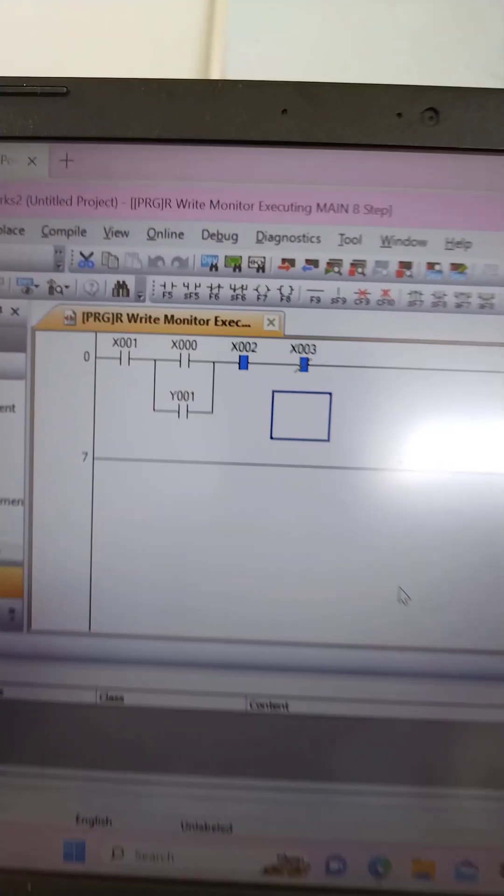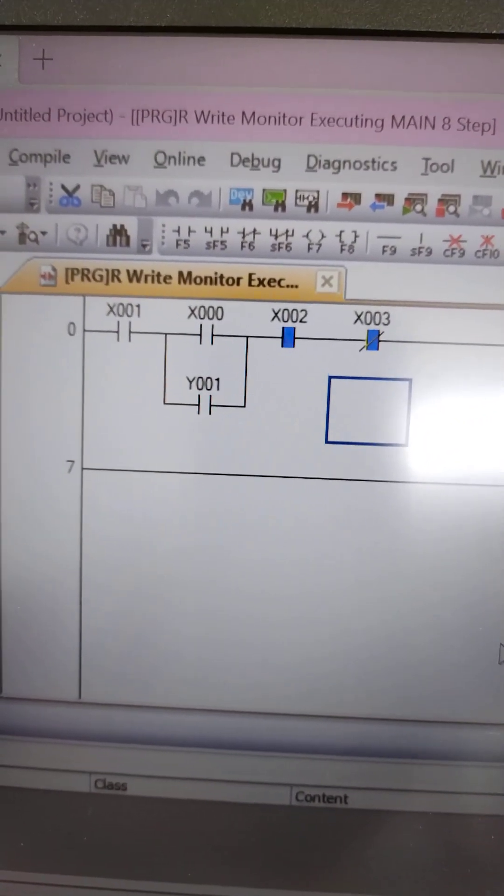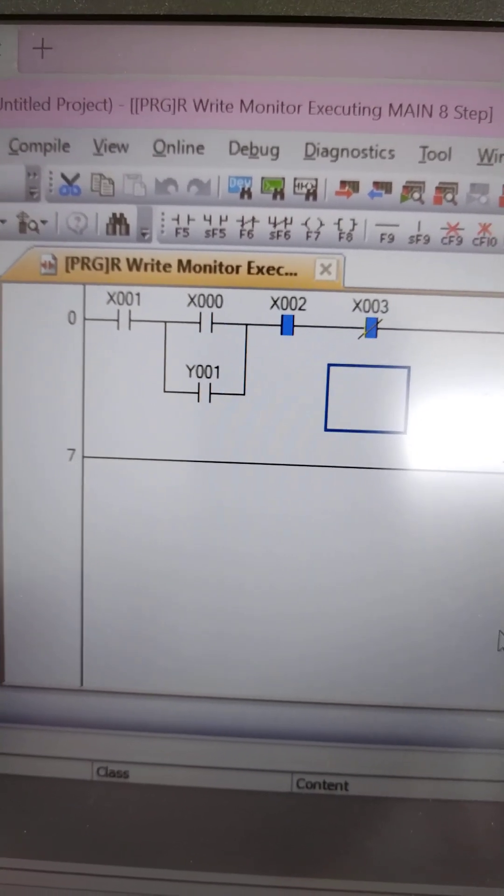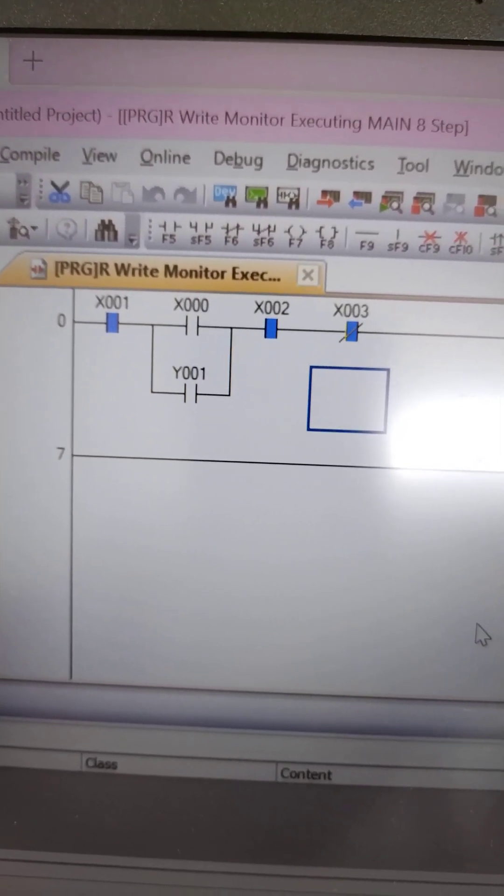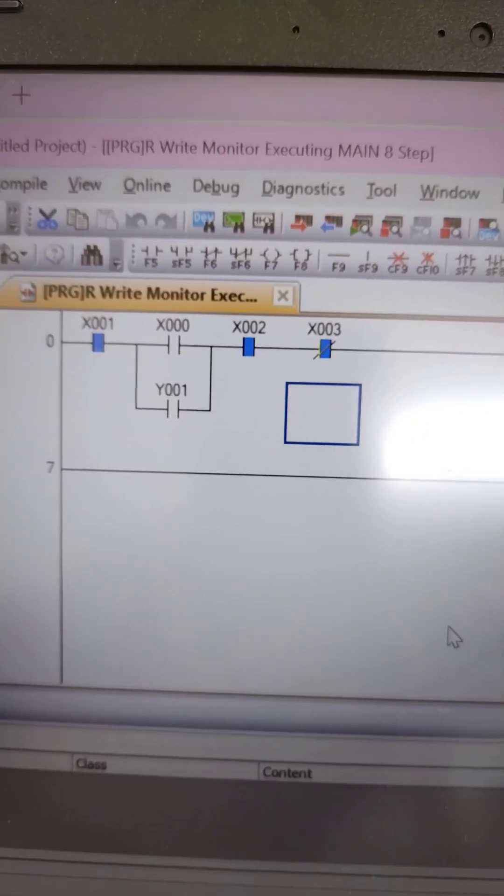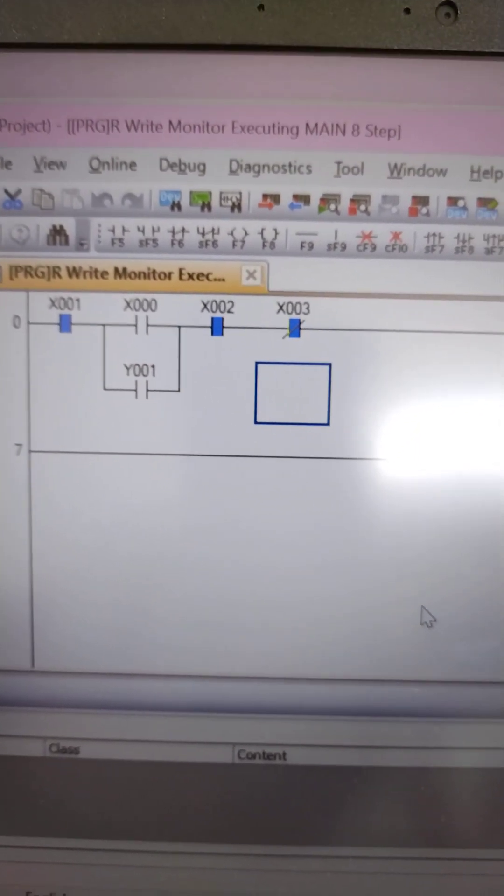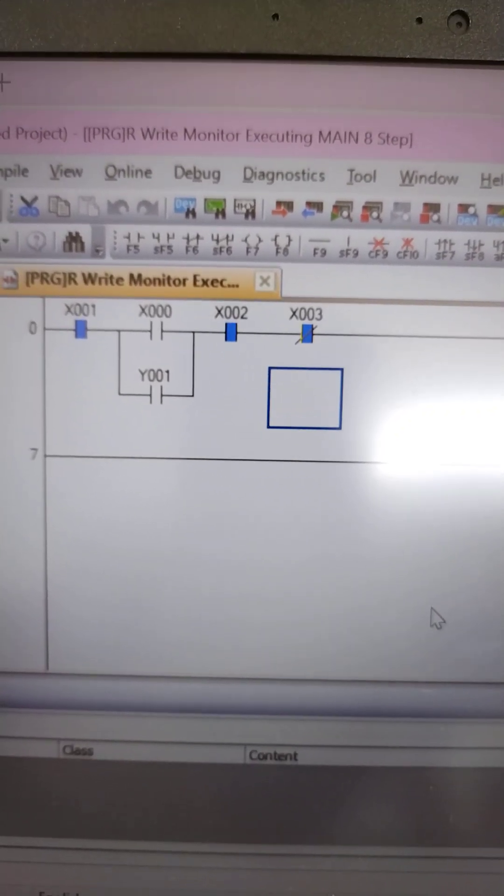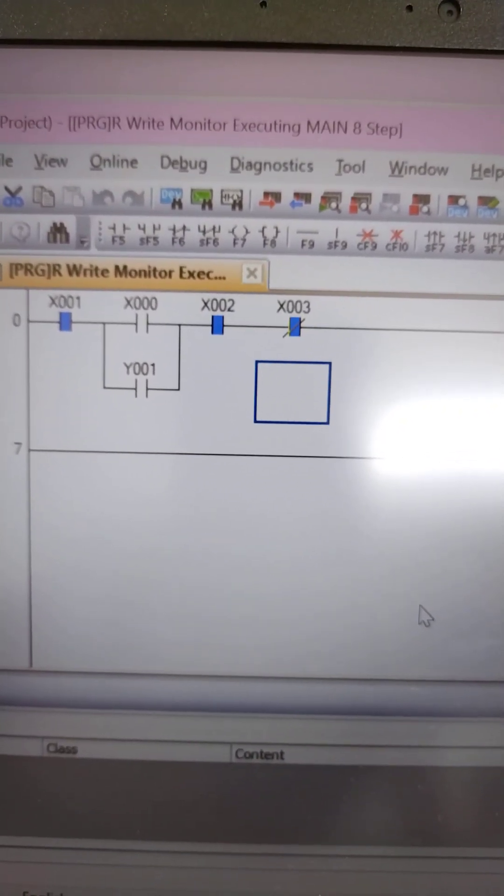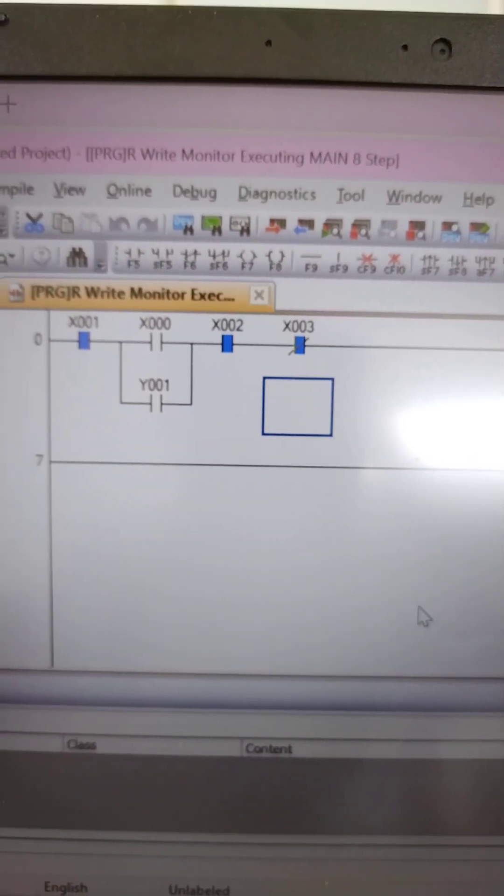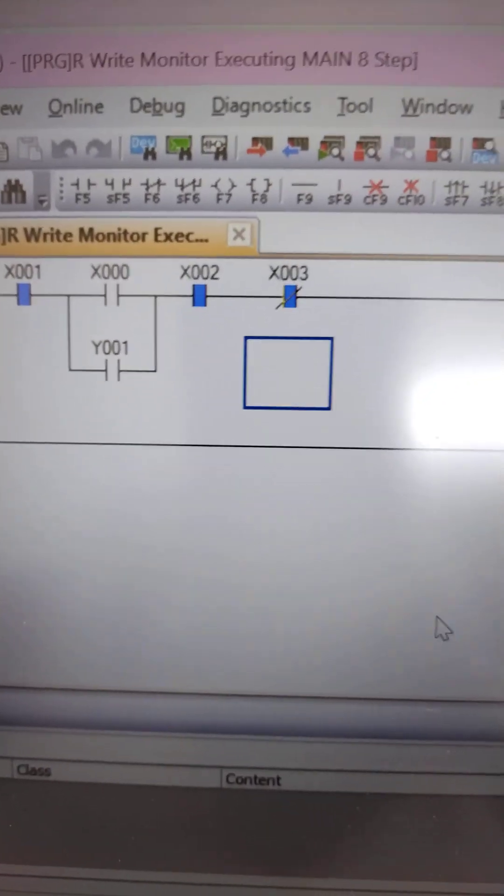So let me show you what I will do. x001 is just like the enable or the selector switch in automatic. As you can see, I toggle the switch. Now it's already in automatic position. Now we are just waiting for the x000, which is the start push button. Then x002 is the stop push button, and x003 is the trip.